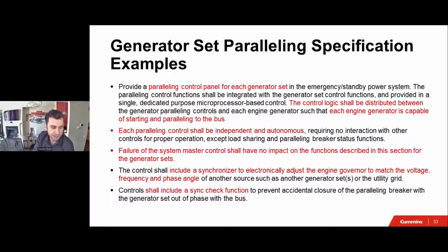They need to be independent and autonomous. That's one of the things that we want to have in the specification. We want to make sure that failure of a system master control does not take them down. So you might still have, like I said, I showed you a picture in the beginning of this presentation of a supervisory control, right? But we want to make sure that there's a time and place for having a system level controller. And we want to make sure that if that system level controller fails, we don't want the generator set controllers to fail as well. We still want to be able for the gensets to come online in parallel and provide power to our loads if we need to.